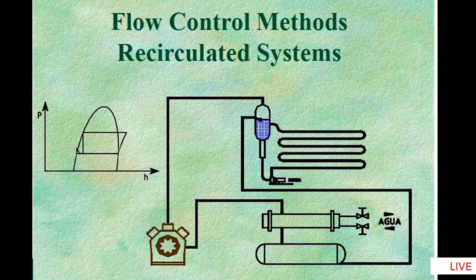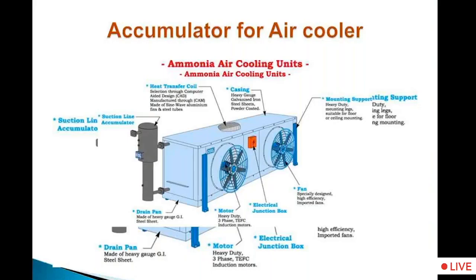This is for flooded ammonia operation, not for pump circulation systems. Wherever you are using a gravity flooded system, the accumulators are used. Where to locate the accumulator, what should be the height of the accumulator, etc., is a separate subject which needs, as I mentioned, another lot of discussion. This is an air cooler with an accumulator. If you ask an accumulator manufacturer or an air cooler manufacturer, he normally avoids giving the accumulator. He says, no, accumulator design is a system designer's responsibility. My responsibility is to give the air cooler. So accumulator design is very, very important.